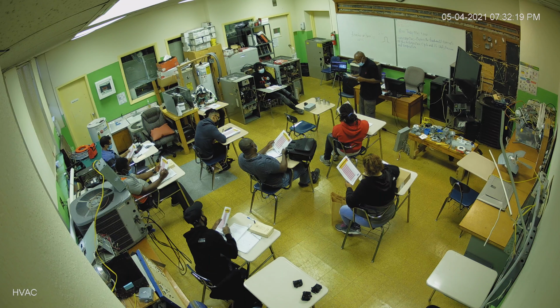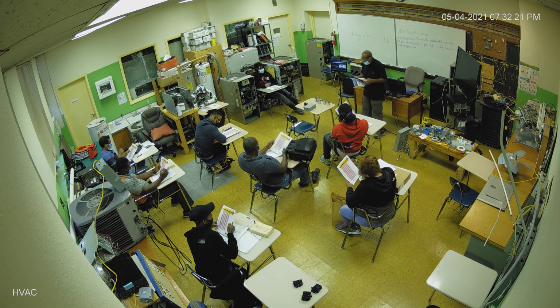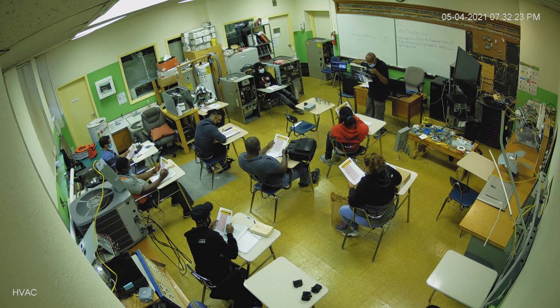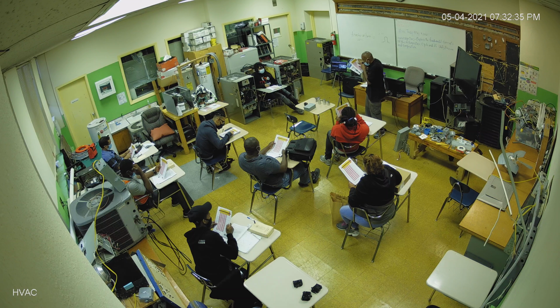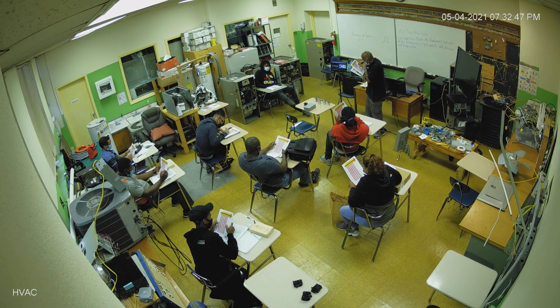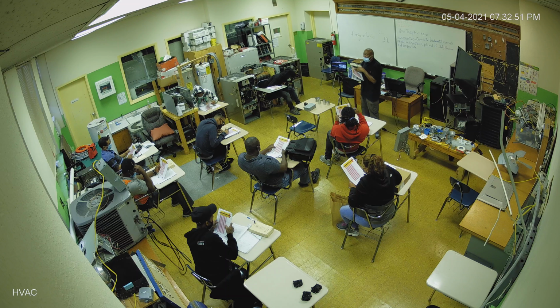Okay, now if we're using 410A, where's 410A? Okay, that's almost at the end, 410A. Just come down to 40 degrees and you'll see what the pressure is. 40 degrees? Yeah, it's 118. Now that's your suction pressure now.